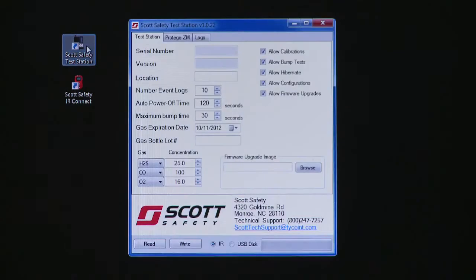Start the Scott Safety Test Station application on your computer. Using the Scott Safety Test Station application, you can program the settings for the test station and the monitors. On the Test Station tab of the application, you can change the settings for the test station itself. Settings such as which test to allow, the number of logs to save, the auto power off timer, the amount of time for a bump test, and the calibration gas settings. Click the Write button to save these settings on the test station.